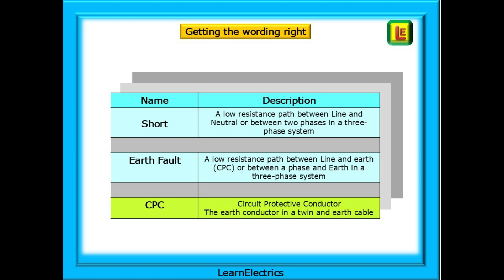We should begin by getting the wording right, especially if you are studying electrics and about to sit an assessment. A short is a low resistance path between line and neutral, or between two phases in a three-phase system. Then we have an earth fault — a low resistance path between line and earth or CPC, or between phase and earth in a three-phase system. It's a short, yes, but it does have its own name. A reminder that the CPC, or circuit protective conductor, is the earth conductor in a twin and earth cable.